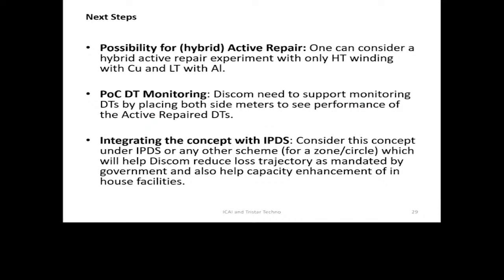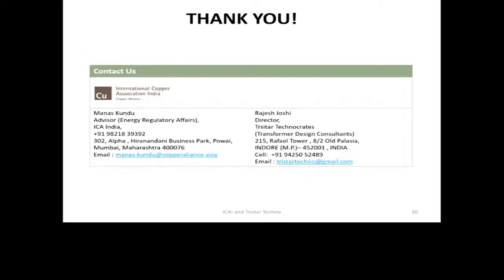According to it, a 2 to 5 year payback period is seen after the active repair is carried out. So it is possible to have a hybrid kind of active repair, where one can replace only the HT or only the LT winding. Depending on that, we have to analyze before going for the active repair. But at least by replacing one of the windings, we can gain the benefits of copper by way of increasing the life, reliability, and energy efficiency.